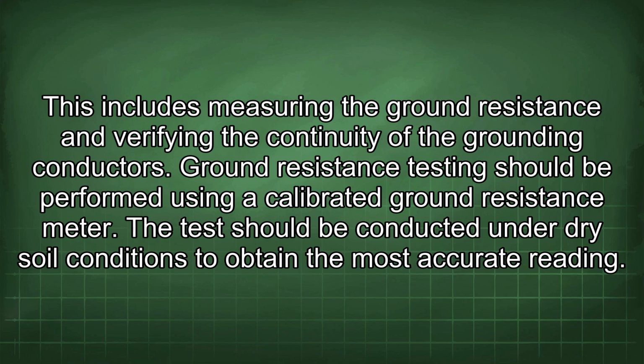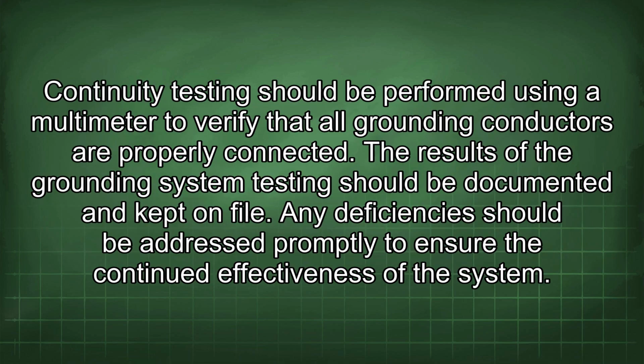This includes measuring the ground resistance and verifying the continuity of the grounding conductors. Ground resistance testing should be performed using a calibrated ground resistance meter. The test should be conducted under dry soil conditions to obtain the most accurate reading. Continuity testing should be performed using a multimeter to verify that all grounding conductors are properly connected. The results of the grounding system testing should be documented and kept on file. Any deficiencies should be addressed promptly to ensure the continued effectiveness of the system.